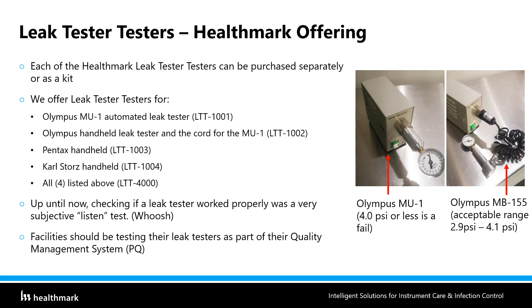Because of the issue we had with endoscopes not being leak tested appropriately, we designed these leak tester testers, or LTT, with which you can verify the various leak testers, and we made them for various manufacturers. For example, in this case, we're talking about Olympus. You need at least 4 psi if you go directly, and if you have the attachment MB155, 2.9 to 4.1 psi. We made those for Olympus, for Pentax, Storz, and other ones. Here, for example, we have some that show at least about 6 psi. You see various ones that have a gauge.